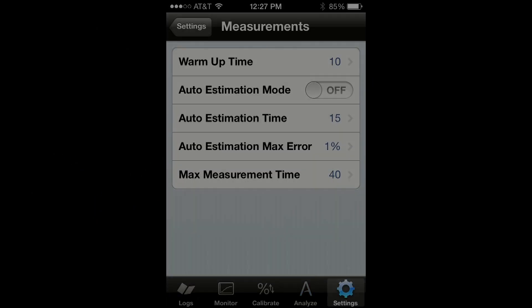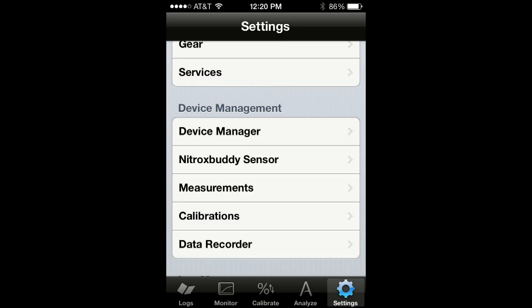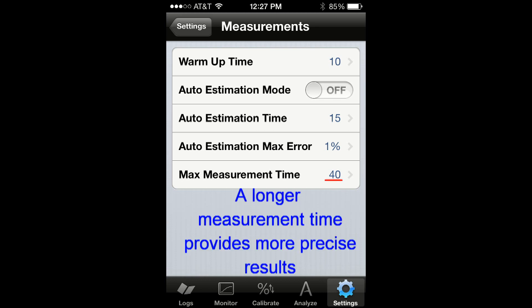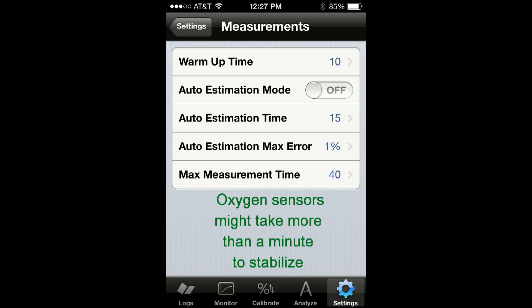You can program how long it should take to complete an analysis, and you can also program the precision of the measurement. To do so, just go to the settings and tap on Measurements. Every measurement has a warm-up period and a maximum measurement time. The longer the measurement time is, the more precise the analysis will be. This is because oxygen sensors are chemical devices and they might need some time to react to changes in the partial pressure of oxygen.